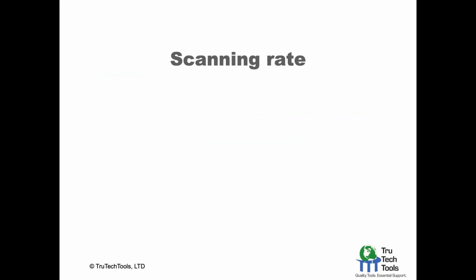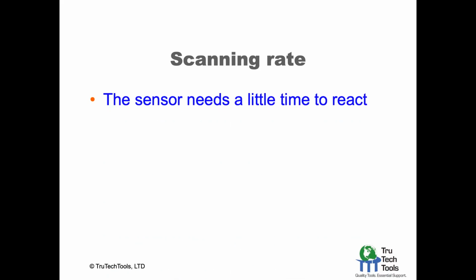So when using this product, again, the users are involved. It was designed a certain way, but there's a person using it. So you've got to know how to scan in order to get effective use of the product by the way it was designed. The sensor does need a little bit of time to react. They're not instantaneous. It's not sensing light or anything like that. The gas actually has to make its way to the sensor, and it has to burn and change the concentration on the sensor and then be reacted to on the display. So moving it too quickly can result in missing things.